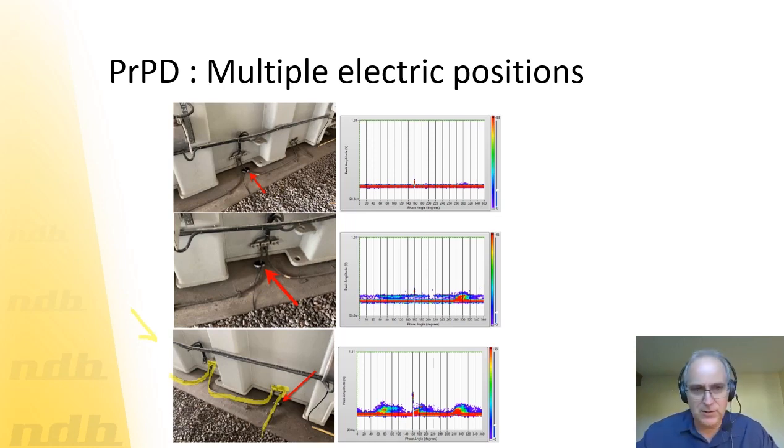Okay, it's not unusual to have more ground connections on the transformer, and it may have more than that, but that's a real example. So I was taking measurement number 1 on this section of the ground, and you see little bumpy things over here and over here. So is it the worst, or is it the highest amplitude that I can get? That was my question. The answer was unknown at that point.